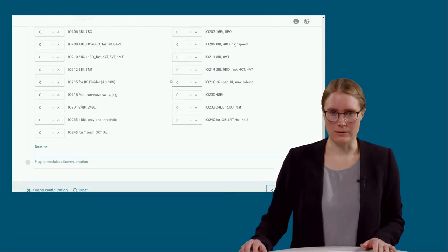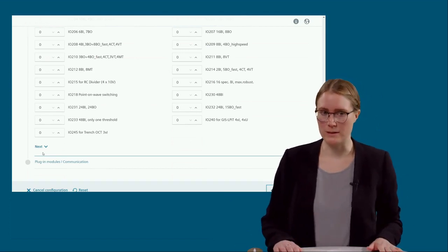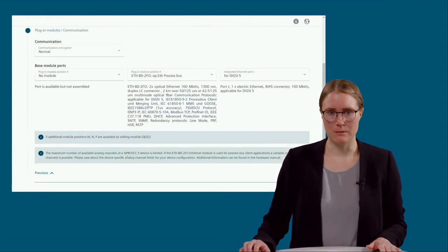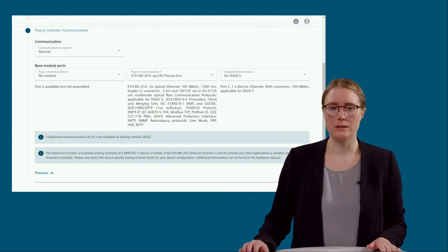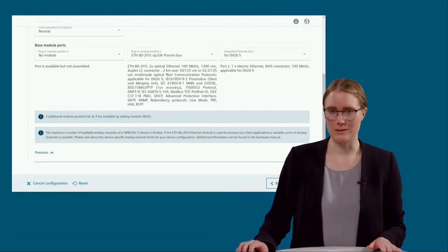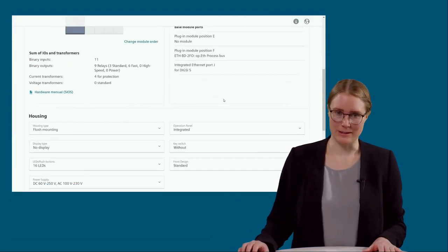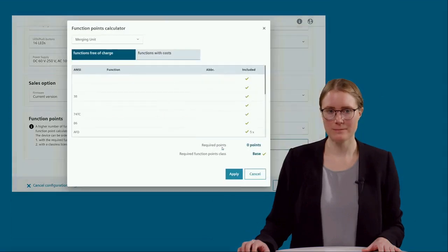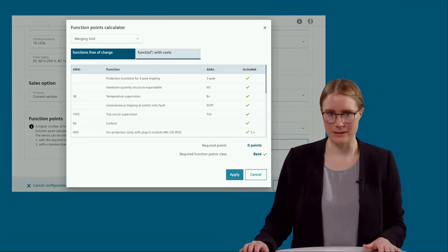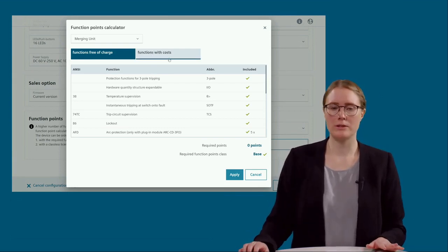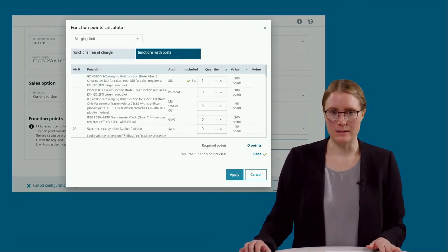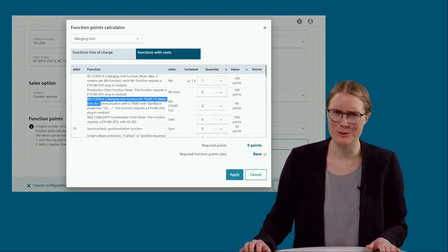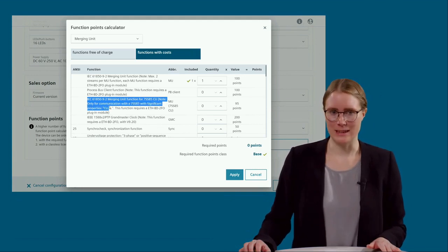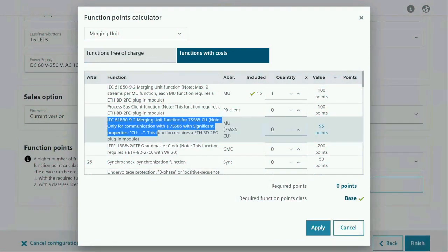We don't need further expansion modules, only if we, for example, have more than one CT in one bay. I confirm this step. We already have one Ethernet BD module, which is also sufficient for our configuration. So I go to the next step. And here I scroll once again directly to the function points calculator. Okay, and here I want to show you the function points for the merging unit device. And here it is the third point I want to show to you, because here the IEC61850-9-2 merging unit function for the 7SS85CU solution costs 95 function points. And these 95 function points are mandatory if you want to use the merging unit in this setup.